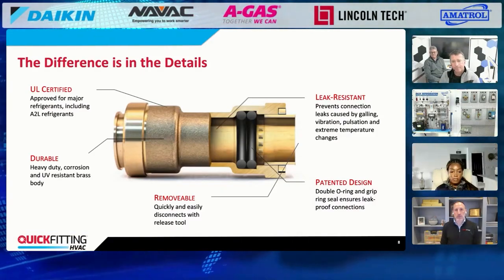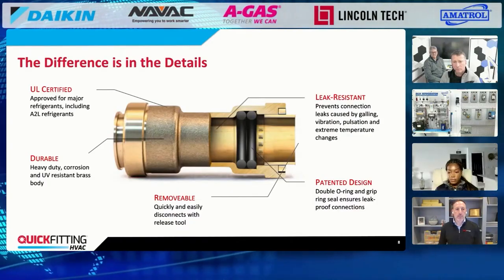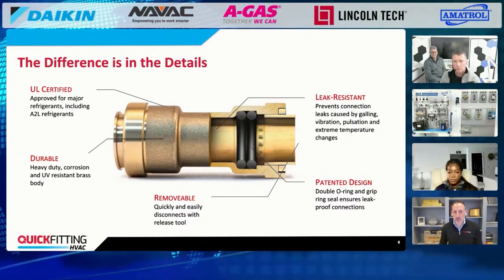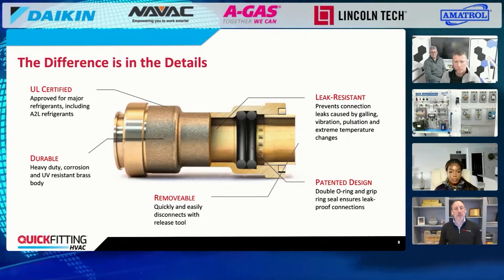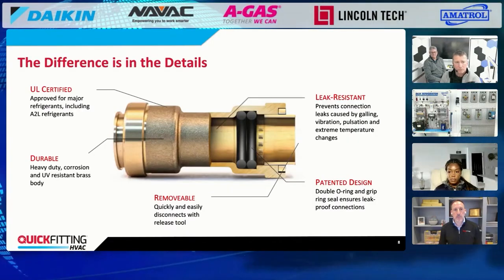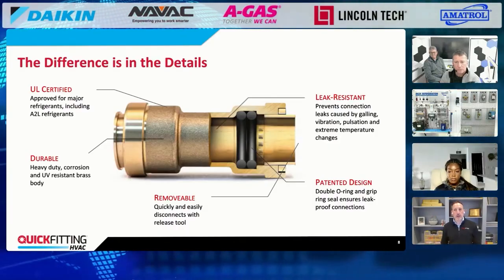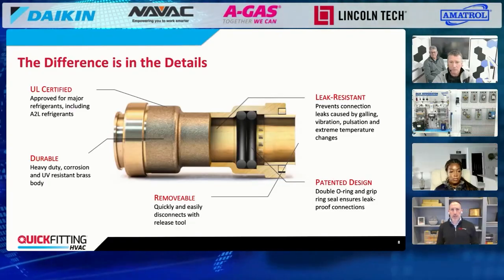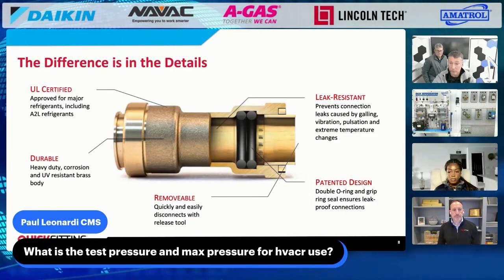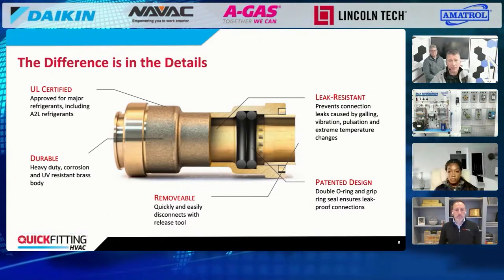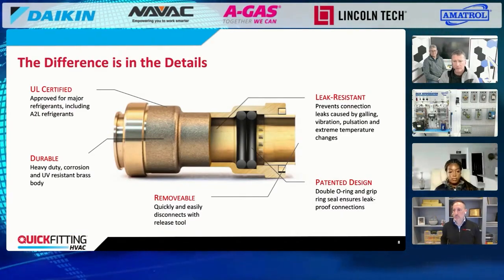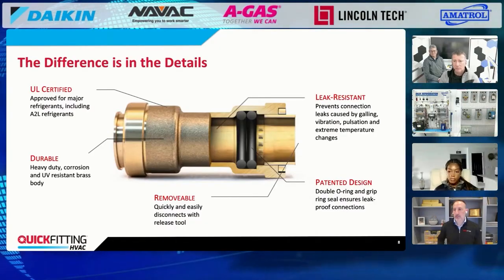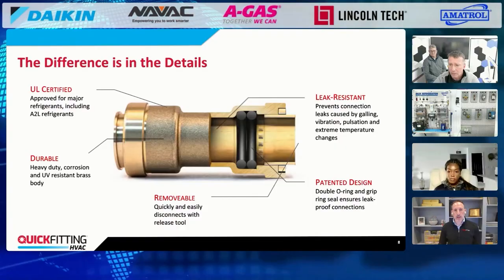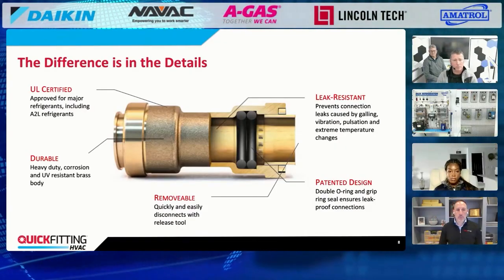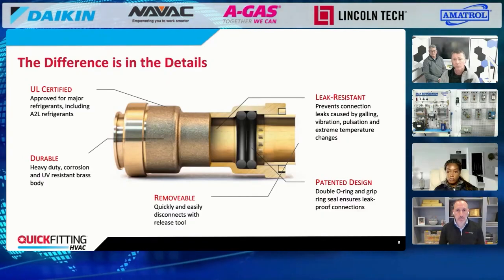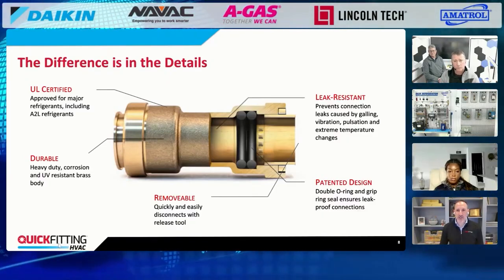We're using brass connections—very reliable, very durable, heavy duty, corrosion resistant. We've put a lot of safety factor into the design of these fittings. Someone's asking about the pressure rating: these are rated up to 870 PSI, much higher than any test pressures from a manufacturer's equipment test rating. These will hold up under stress—we design and test everything to the extreme, and we'll have a photo in a moment that shows how we test it to the extreme.